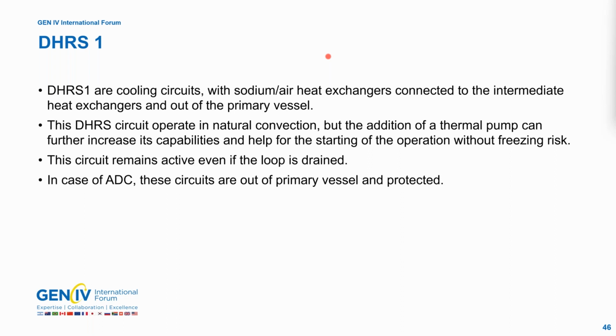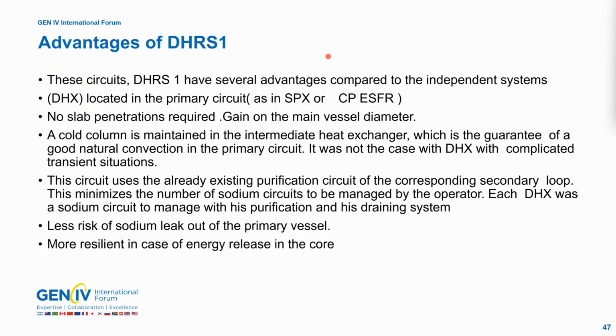And we arrive at the last system, the DHRS1. There are cooling circuits with a sodium-air heat exchanger connected to the intermediate heat exchanger and outside the primary vessel. They operate in natural convection in air and natural convection in sodium. There is a thermal pump on the circuit to increase the capabilities and to help with the starting of the operation. The circuits remain active even if the loop is drained. In case of accident, the circuits are outside the primary vessel and thus mechanically protected, without problems of mechanical release. What are the advantages?